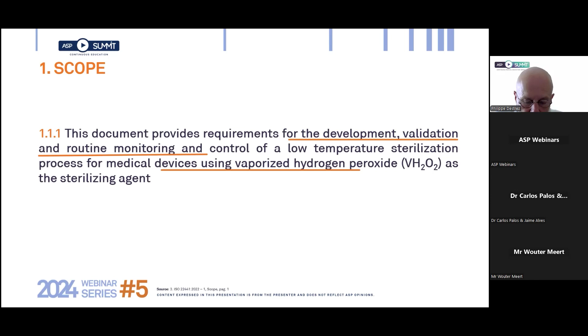When reading a process standard such as ISO 22441, it's important to have in mind that they apply to both healthcare facilities and medical device industries. The two domains are, as you know, very different in practice. In medical device industry, typically the load is always the same and the contamination level is under control. In healthcare facility, loads vary according to surgical activities, and even after careful cleaning, contamination status cannot be guaranteed. This is the reason why the overkill margin, safety margin, is used.